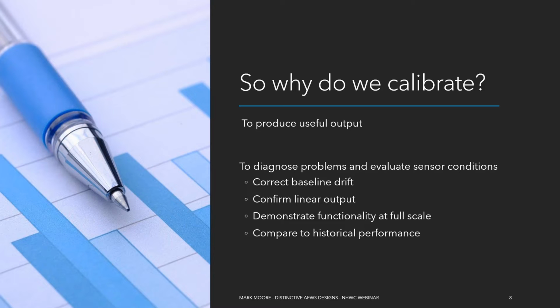I am a big proponent of radars, but one of the issues you could say maybe with radars is you can't really calibrate them across the range. That'd be something that has to be done back in the lab with very expensive high-tech equipment. You are hoping that it works when the water goes up. And again, I'm a big fan of radars. I'm not saying that's a bad thing, but one of the nice things about pressure transducers is that you can test yourself that it works when the water goes up. And last, you can also compare it to historical performance. How long has the PT been accurate? Are we seeing a drift of it being less accurate, more accurate, etc.?